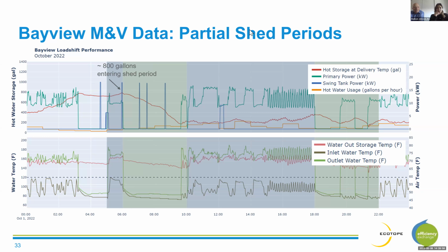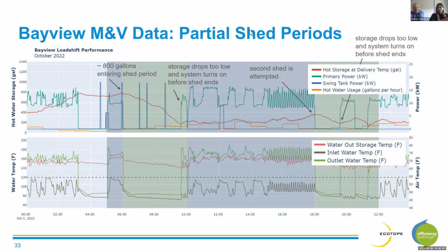So as we enter our morning shed period, we have around 800 gallons of available hot water stored up. And we do make it almost all the way through the shed period. You'll see that red line dips pretty low, and that triggers the system to turn on before the shed period is over. We do have a little bit of difficulty loading up on this particular day during the afternoon. Despite that, the system does still attempt a second shed period. However, we only make it about a third of the way through before the system does turn back on.